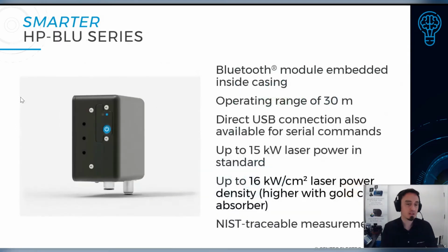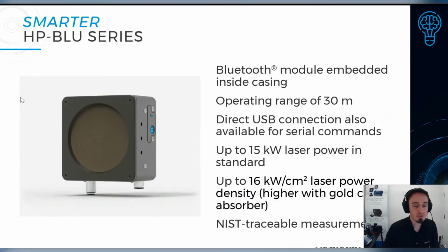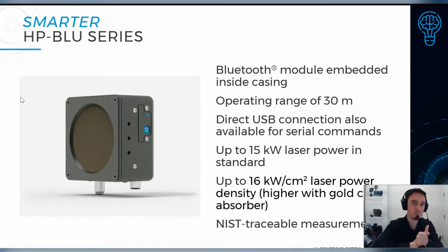Okay, so like I mentioned, the HP-BLU series. So you have the Bluetooth module that's embedded inside the casing. So slick design, operation up to 30 meters. You have as well the direct USB connection still available for using serial command for automating your measurement, for example. This series goes up to 15 kilowatt of laser power in standard and up to 16 kilowatt per square centimeter of laser power density. We do offer higher than that with a gold cone kind of absorber, not the flat one that you see here, with the wireless measurement capability as well. And as always, NIST traceability comes with these features.